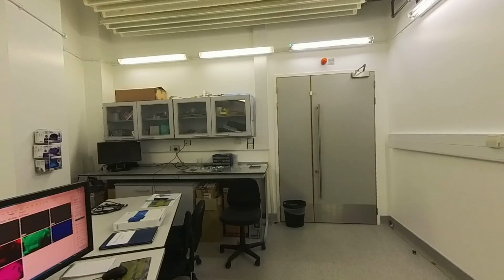So you can see here, it's quite small. And we load our stubs into our sample chamber here. I'll then close the sample chamber, and all of the air is now being sucked out of this chamber to form a vacuum where we have no air particles in there at all, and it's a completely empty space.